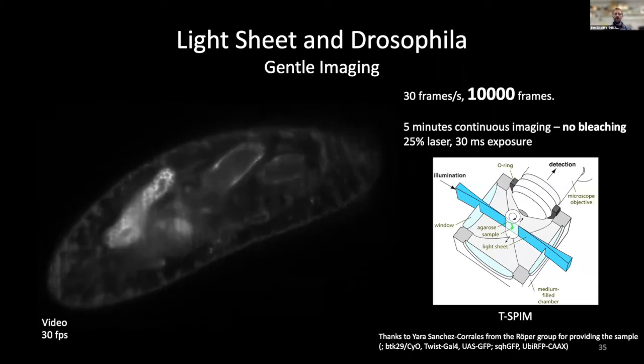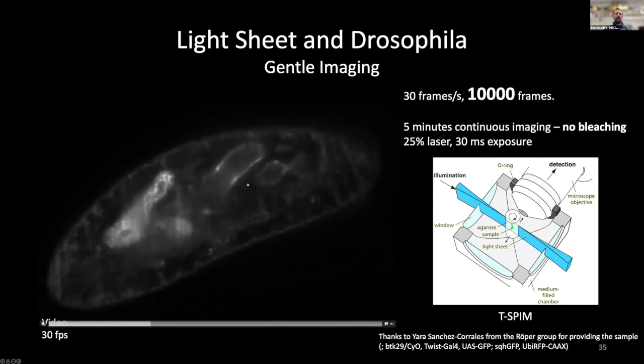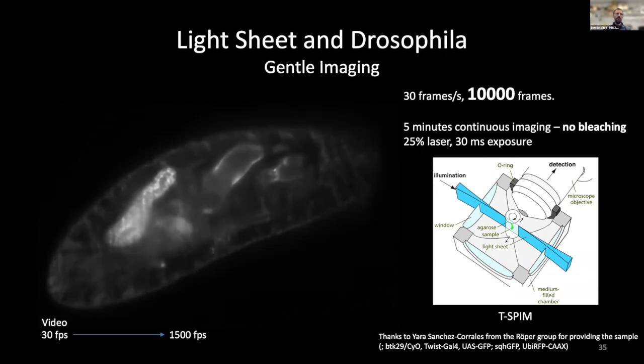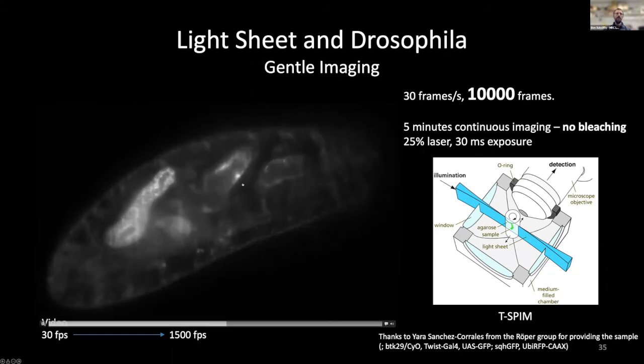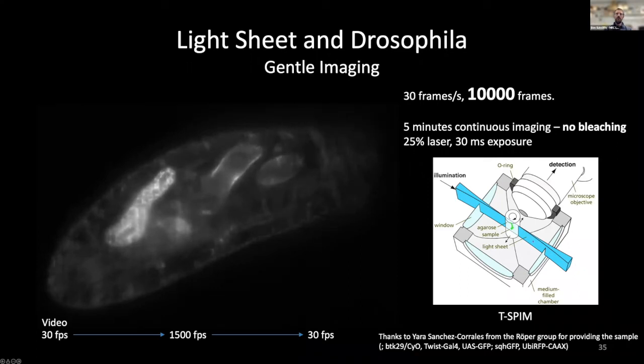Here is an example of how gentle light sheet imaging can be. This is a living Drosophila embryo undergoing peristalsis, imaged continuously for five minutes at 30 frames per second — 10,000 frames — with no bleaching of the sample. The middle section is sped up so you can see that at the end, brightness is the same as at the start. This would have bleached very rapidly on a confocal microscope. This was acquired on a T-SPIM arrangement with dual-sided illumination and detection.